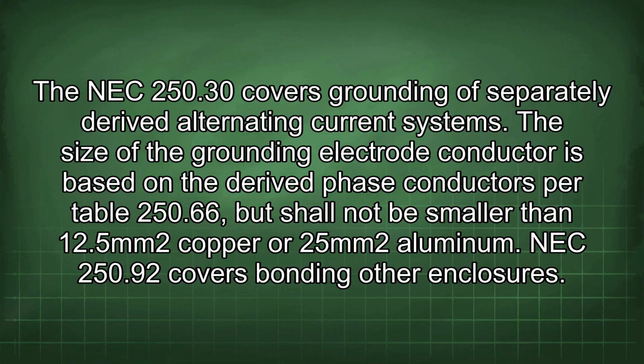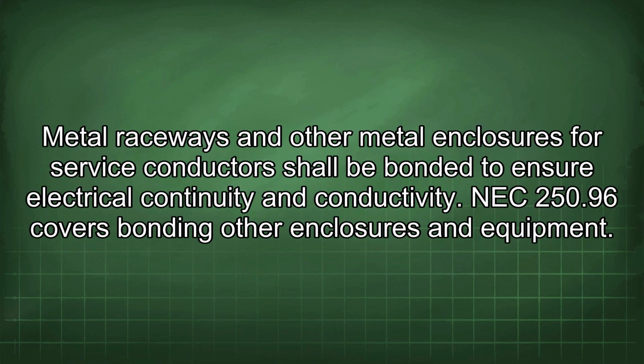NEC 250.92 covers bonding other enclosures. Metal raceways and other metal enclosures for service conductors shall be bonded to ensure electrical continuity and conductivity.